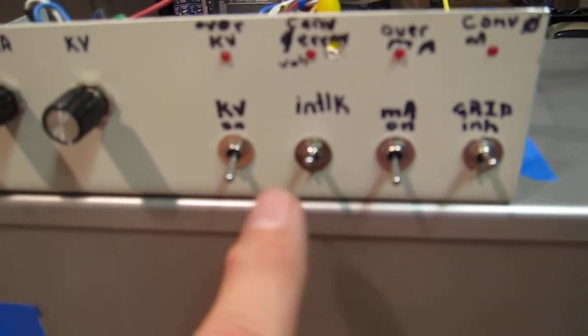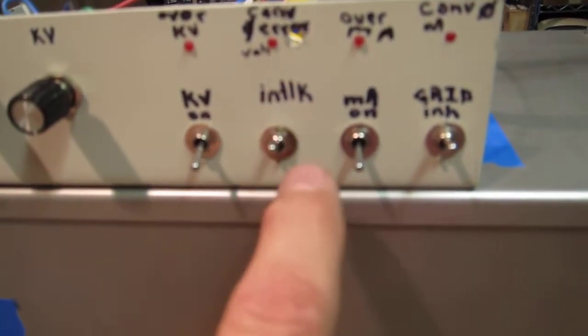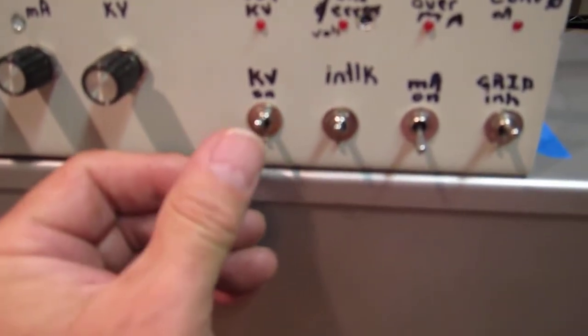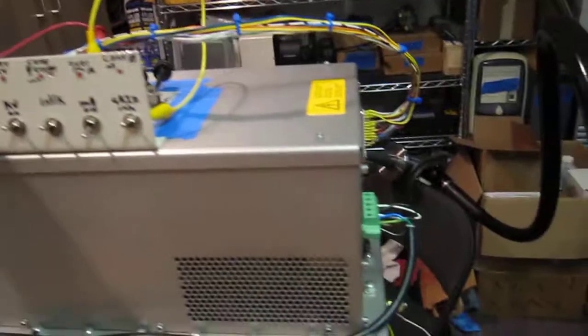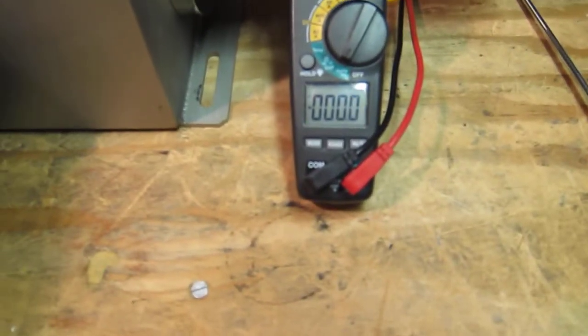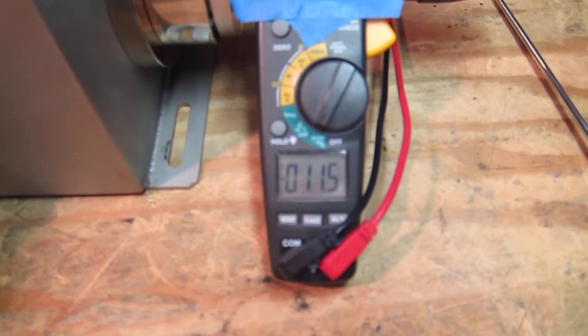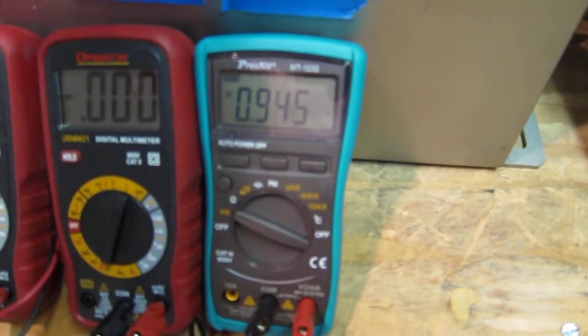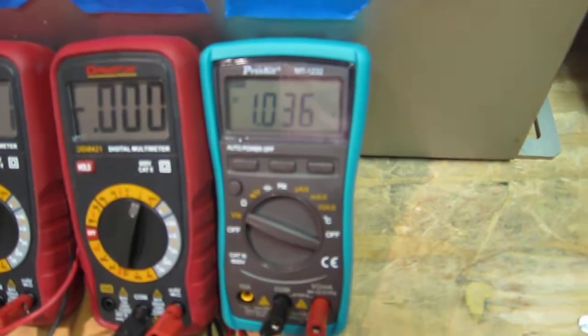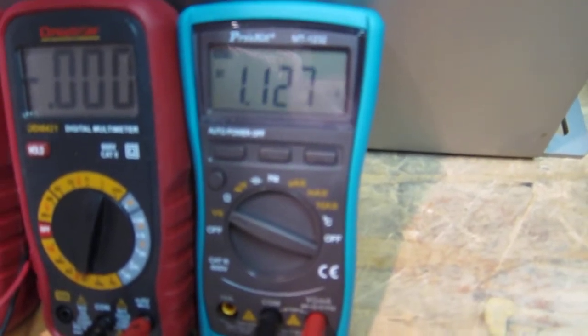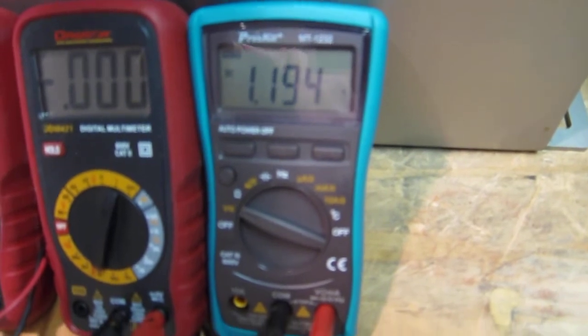Okay, so I've enabled, I've closed the door on the X-ray machine by flipping this interlock switch, and then I make sure that all these potentiometers are turned to minimum, and I'll enable the high voltage, and then slowly increase the high voltage knob, and there I've got 11 kilovolts, and climbing. And here, when I get to 1 volt approximately on this meter, that should be about 16 kilovolts approximately. It could be something more like slightly different scaling, but of course the computer software can make adjustments.